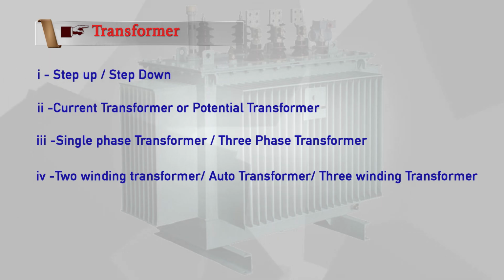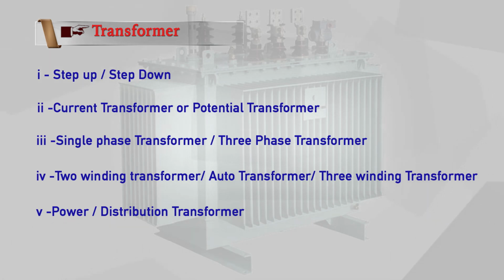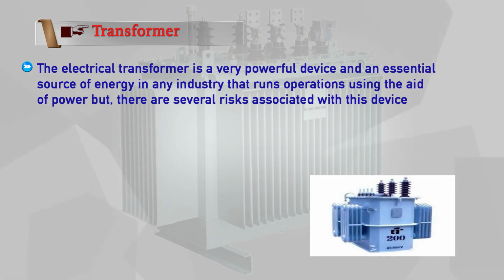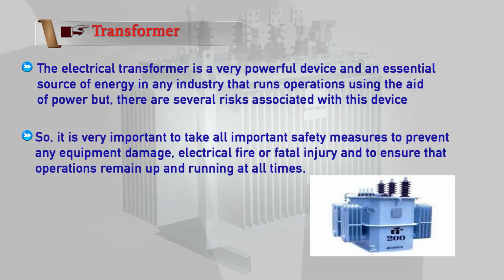Then transformers can be classified as two winding transformers, auto transformers or three winding transformers. They can also be classified as power transformers and distribution transformers. The electrical transformer is a very powerful device and an essential source of energy in any industry that runs operations using power, but there are several risks associated with the device. So it is very important to take all important safety measures to prevent equipment damage, electrical fire or fatal injury, and to ensure that operations remain up and running at all times.